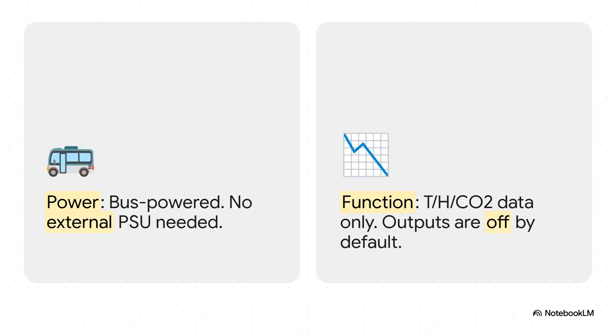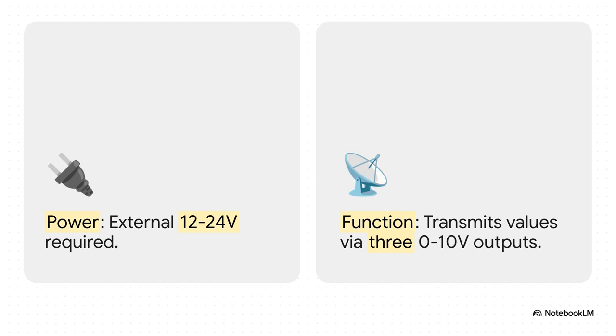Next is M-Bus mode, and this one is super convenient. The sensor is powered directly from the M-Bus communication line itself, so no separate power cable is needed. Super clean install. The trade-off? By default, the analog outputs are off. But, and this is a nice little touch, if you do connect an external power supply, they spring right back to life. Third, you can just forget the digital protocols entirely and run it in pure analog mode.